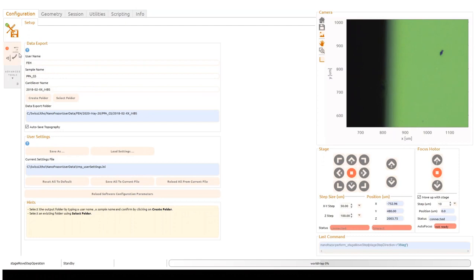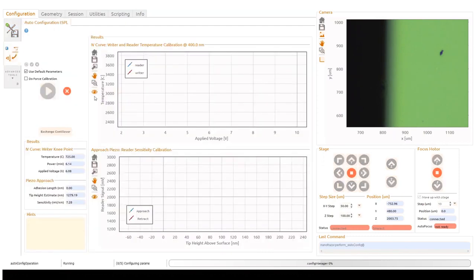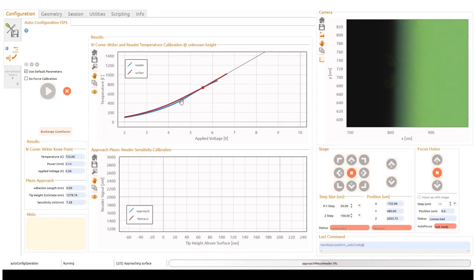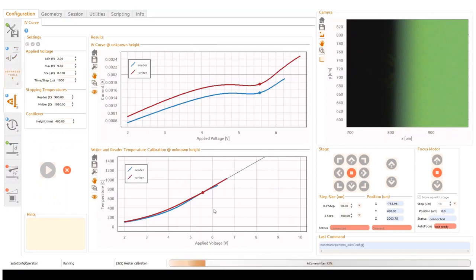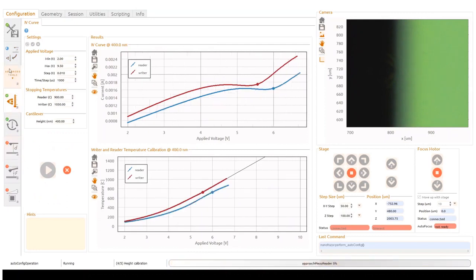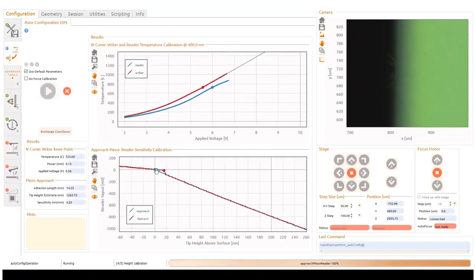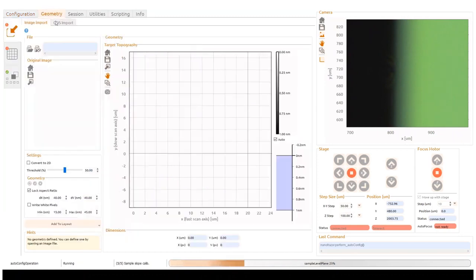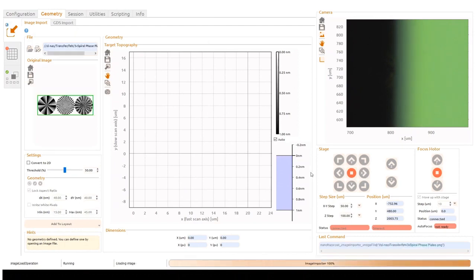You move around here with your cursors, with your coarse stage, to go to the location you want. I set up already the database path where all the data will be saved, and then I press this green button for starting the calibration of this new cantilever. That's the temperature calibration. It's already done. It's doing some more calibration. If you want, you can look at all of them here in these advanced tools.